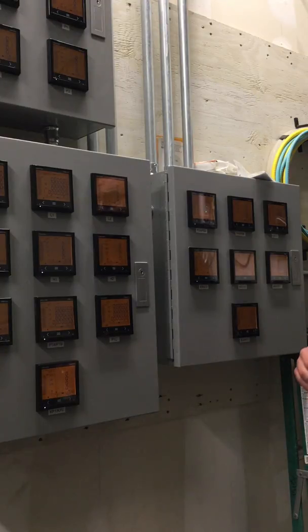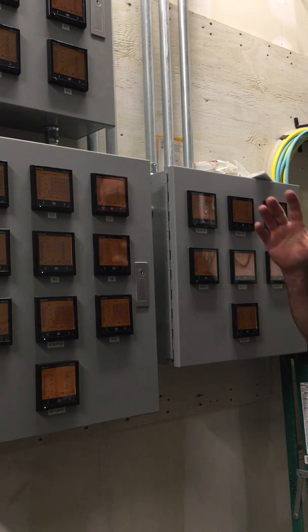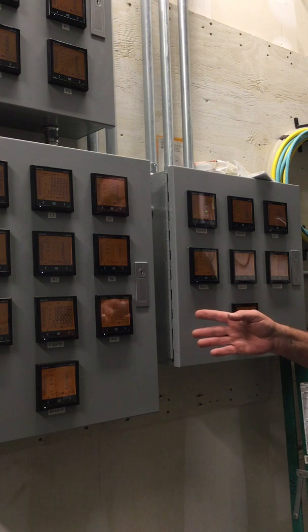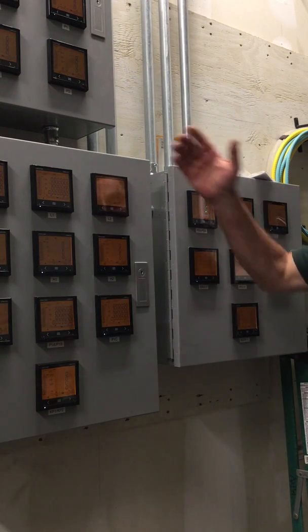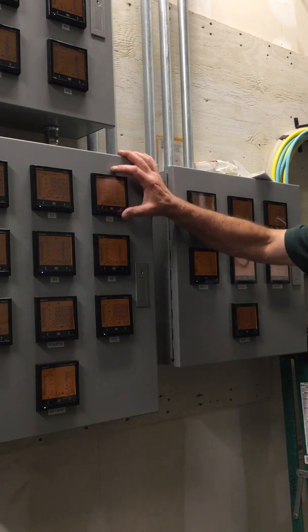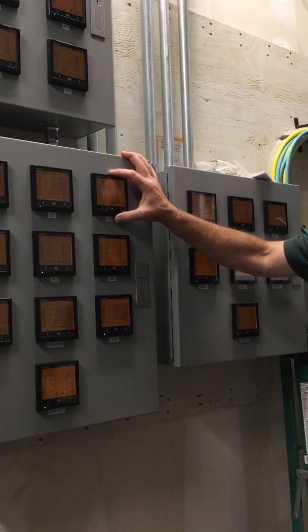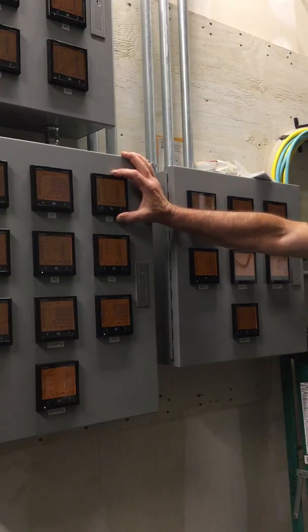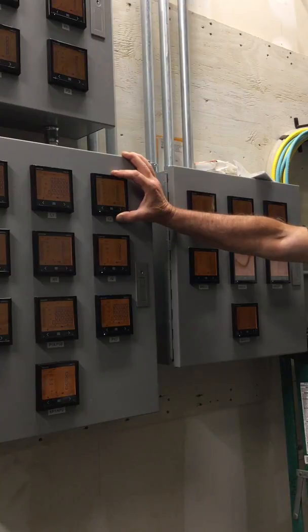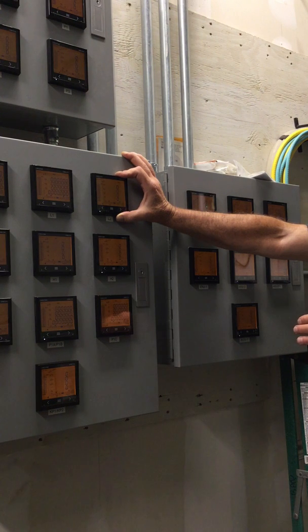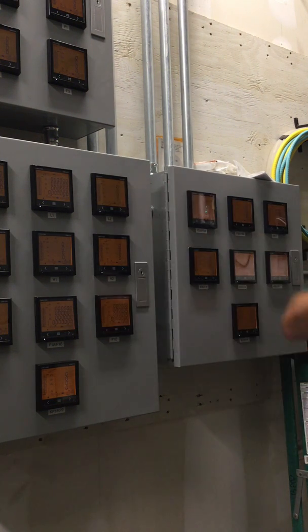that's literally it. Unless you have any questions on power quality or parameters, the meter will do its calculations until it goes out of calibration, and that's, again, a checksumming of the firmware being used against what's in the RAM memory chip. If the meter decides to go bad, it will shut itself off. The other reason it will shut itself off is that there's a transformer in the meter that brings power from the auxiliary power supply down to millivoltage. If that transformer ever decides to have a bad hair day, there are traces on the board that will melt open at less than 0.2 of an amp feeding the primary side of that transformer. So it'll melt open and shut off, but there's no way a fault is going to go to the breaker or fuses that are feeding these meters. It doesn't affect the operation of the breaker. That's just gone.